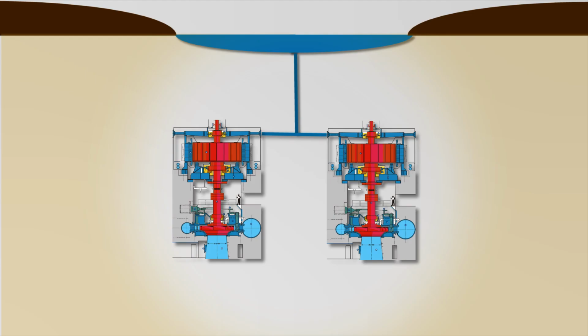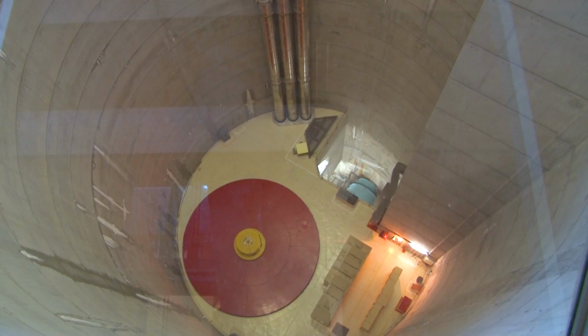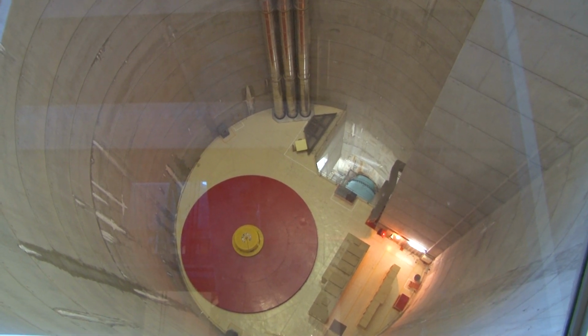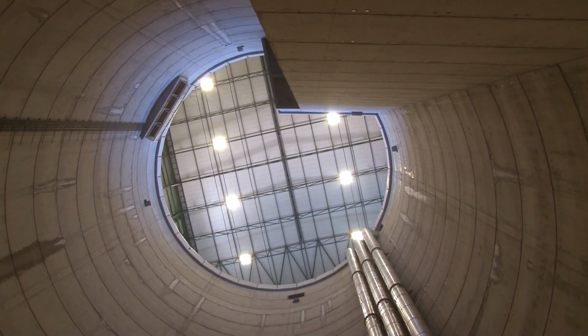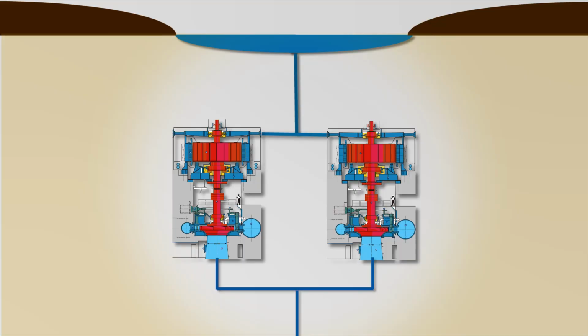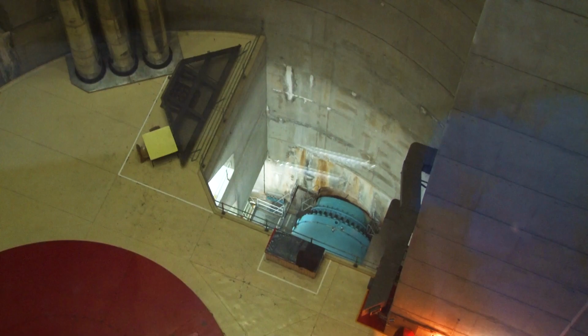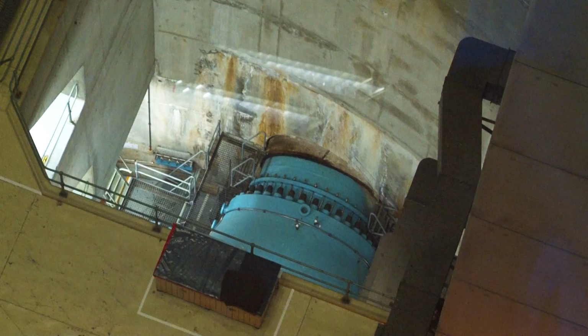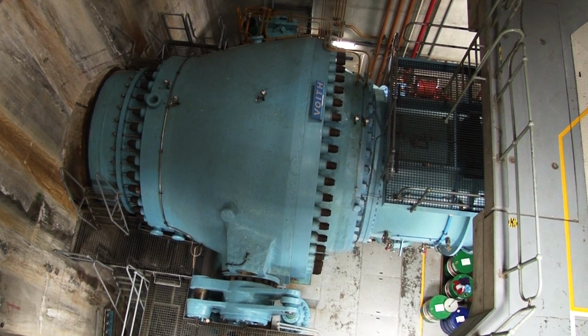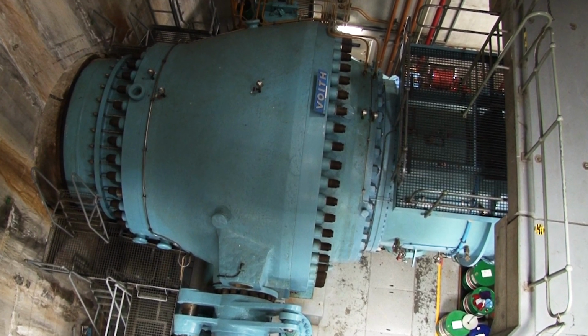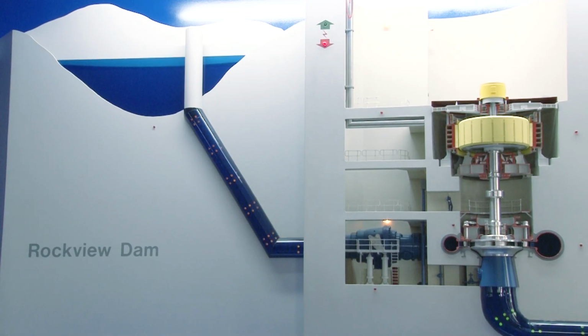The two 200 megawatt generator pump turbines are located 60 meters below ground level at the base of 2 concrete-lined shafts. This is equivalent to a 25-story building. The power station is built almost like a set of rugby poles buried underground. One waterway comes down from the Rockview Dam, splitting just before it enters the station, so that each machine can have water. The water flows into the turbine through an enormous valve, which weighs 180 tons. This valve operates like a tap to control the flow of water into the machine.